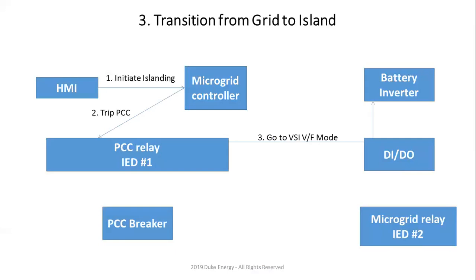The moment we go to the islanding, we have something that is called 85 RIO scheme. 85 is one of those schemes, just like 27, 59, 81. So this one's called 85. It requires DIDO, and I told you the communication is the fastest one using mirror bits, serial and fiber. So the battery has to switch from VSI PQ mode to the VSI VF mode, or what probably everybody else knows as a Duke mode. And then we have to trip the islanding switch.